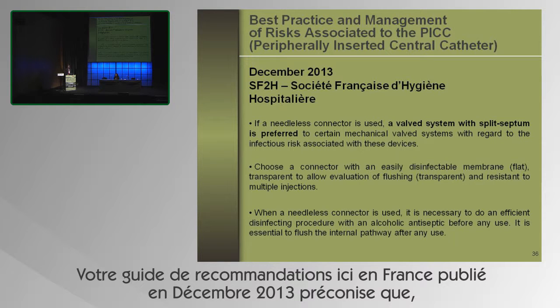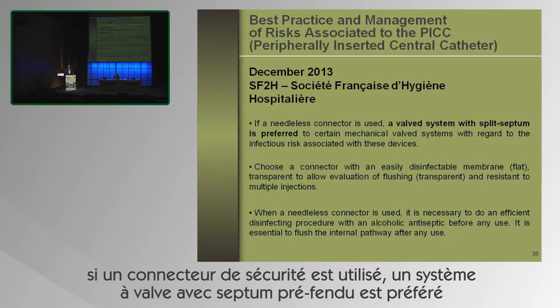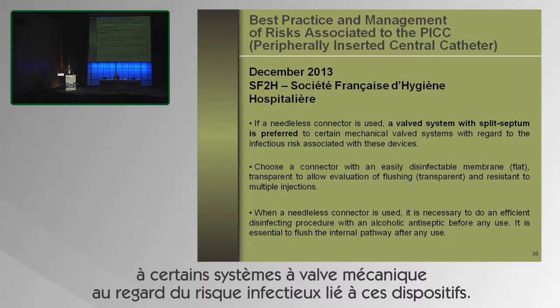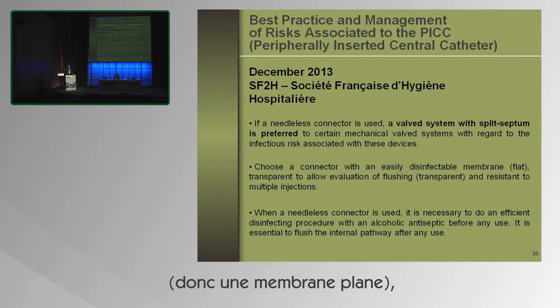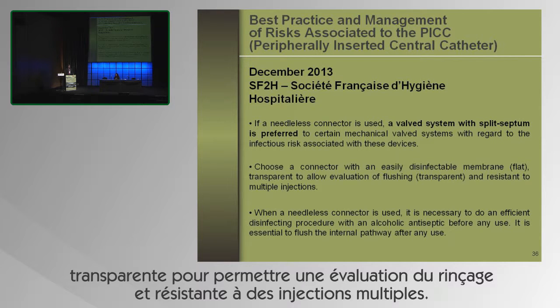Your guideline here in France, published in December of 2013, says that if a needleless connector is used, a valve system with split septum is preferred to certain mechanical valve systems with regard to the infectious risk associated with these devices. And to choose a connector with an easily disinfectable membrane, so a flat membrane, transparent to allow evaluation of flushing, and resistant to multiple injections.